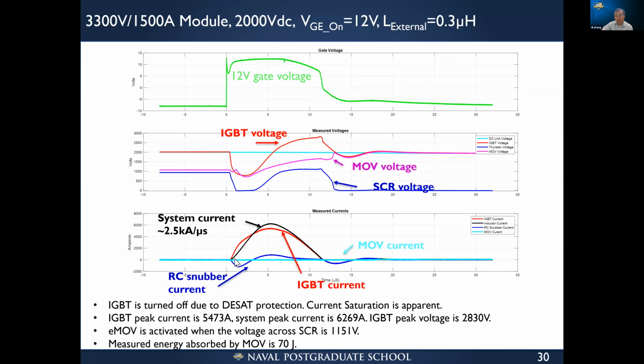Okay, as you can see, when the current is increasing, the IGBT voltage will increase automatically, trying to reduce the current increase. The gate voltage is removed somewhere here, right? You can see the IGBT voltage keep increasing, trying to limit the fault current automatically. And because of this, the peak IGBT voltage during switching is only 2800 volts, which is still below the 3.3 kilovolt voltage rating. In this case, the MOV is activated when the voltage reaches about 1151 volts. However, as you can see, in this case the MOV doesn't help too much, right?